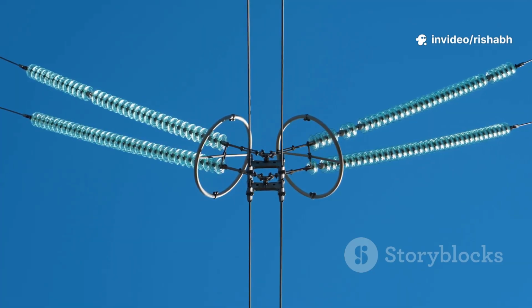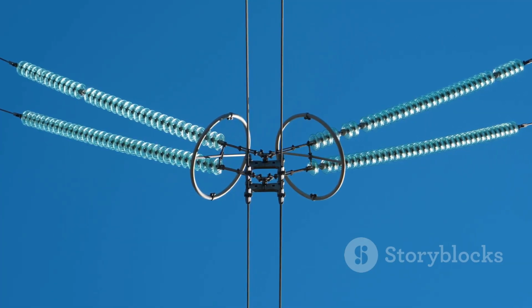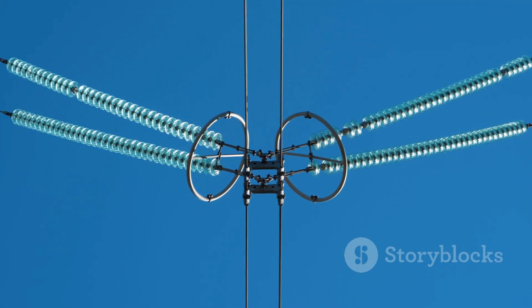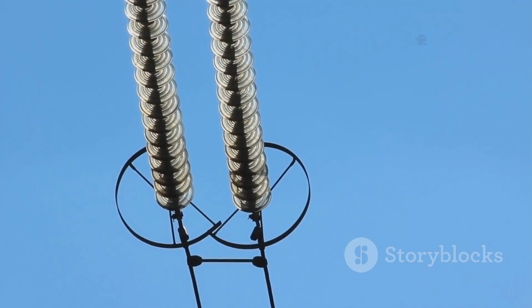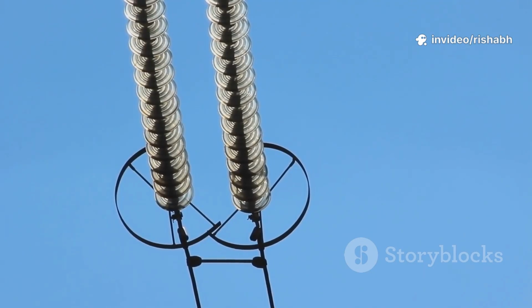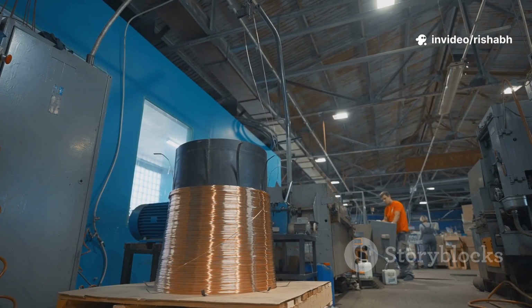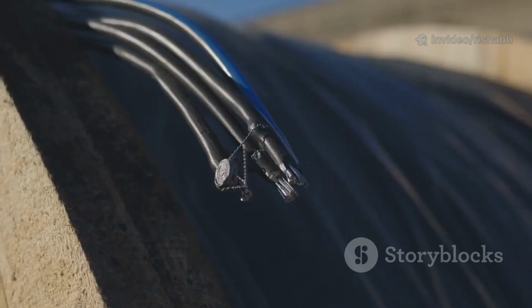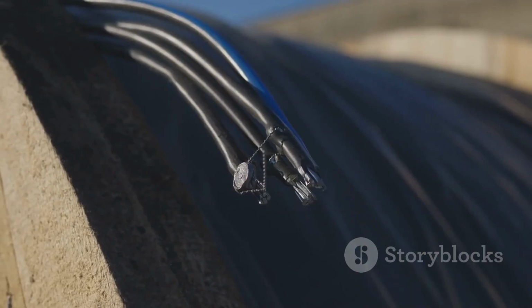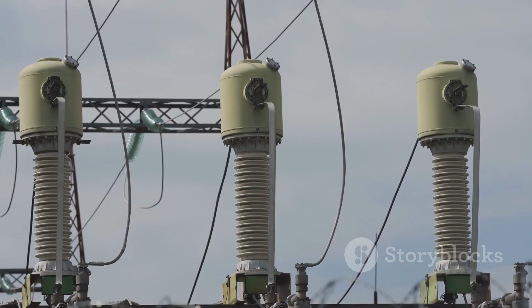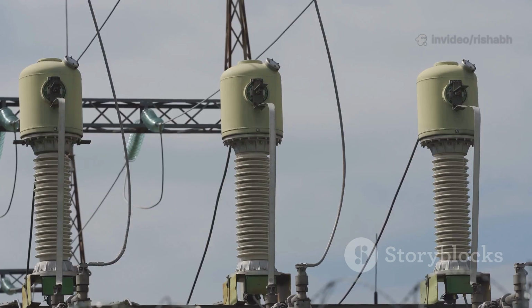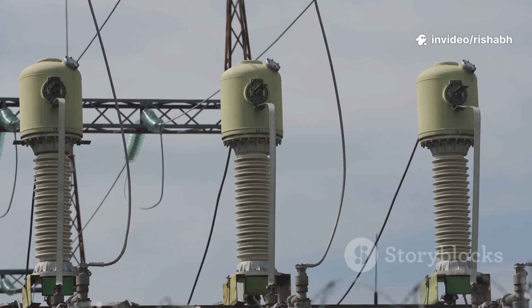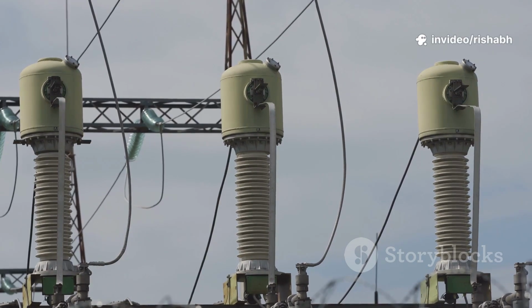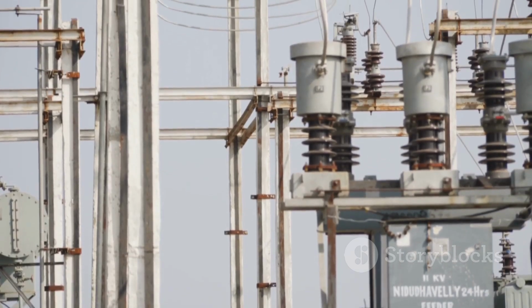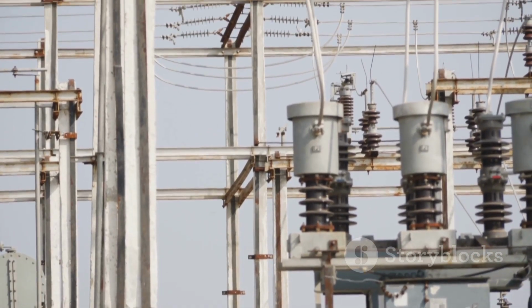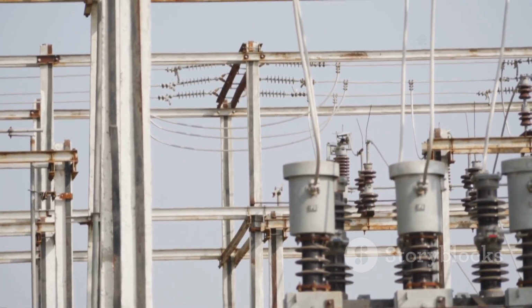High-voltage bushings use a more sophisticated design, known as a condenser or capacitor-graded bushing. Inside the main porcelain or composite insulator, the conductor is surrounded by a series of concentric conducting layers, typically made of aluminum foil. These layers are separated by insulating paper. This structure acts like a series of capacitors, distributing the electric field smoothly and evenly along the length of the bushing, both internally and externally.